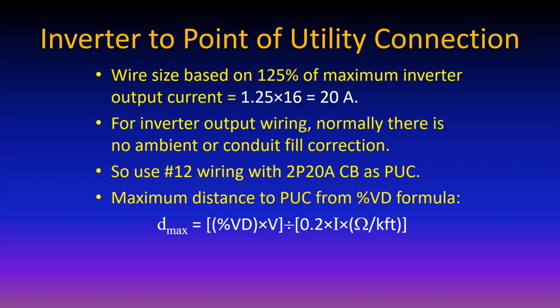Here's the formula for it. I knew you'd all want to have at least one formula. So the maximum distance is the percentage voltage drop that you're willing to accept, and that as a number, 2, not 0.02, not 0.04, because that's all taken care of in that 0.2 in the next term, times the operating voltage, 240, times 0.2, times the operating current, 16, times the ohms per 1,000 feet of that wire, which you dig out of chapter 9 of the NEC, in the tables.